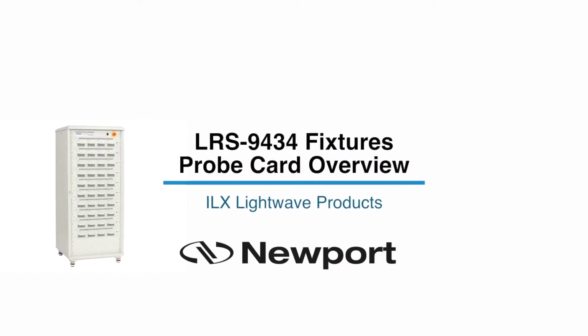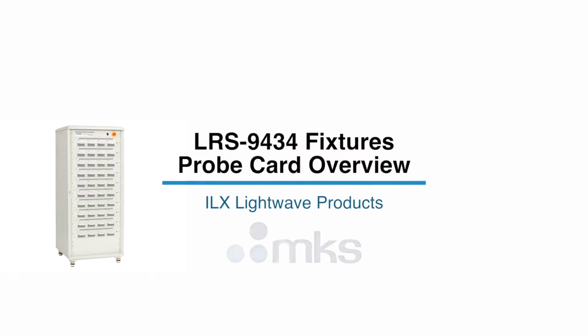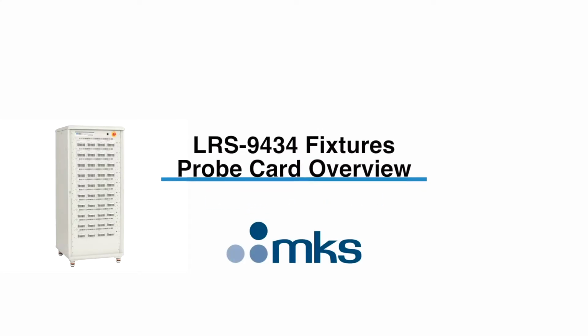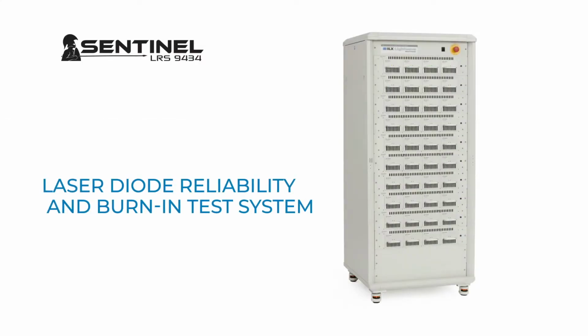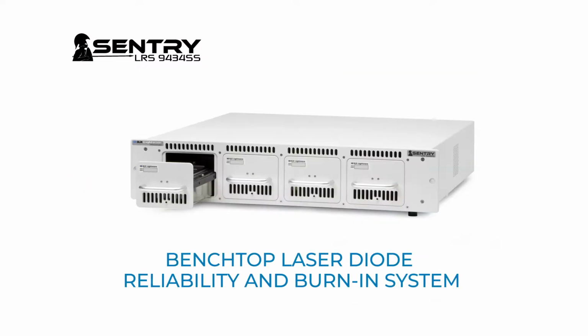MKS's ILX Lightwave LRS-9434 test systems are used for laser diode testing based on a modular architecture. The Sentinel LRS-9434 has a rack which can hold up to 11 control measure modules, or CMMs. The LRS-9434SS is a standalone CMM, or single shelf, of a Sentinel LRS-9434. These CMMs can control and monitor up to 4 fixtures.